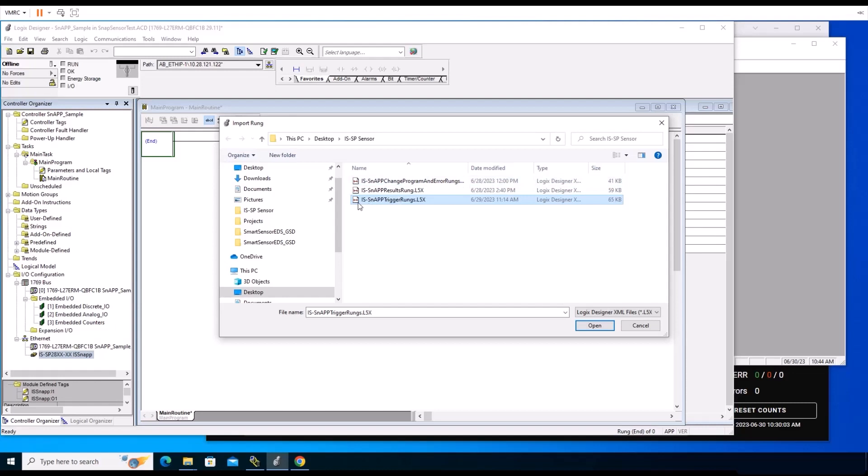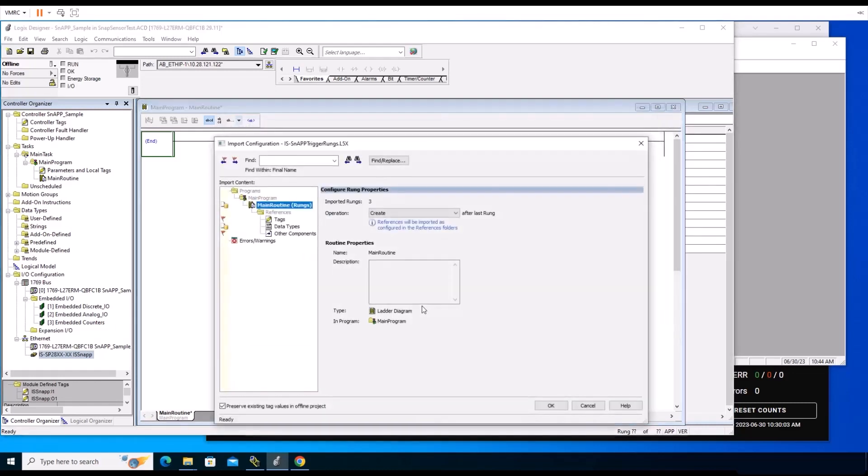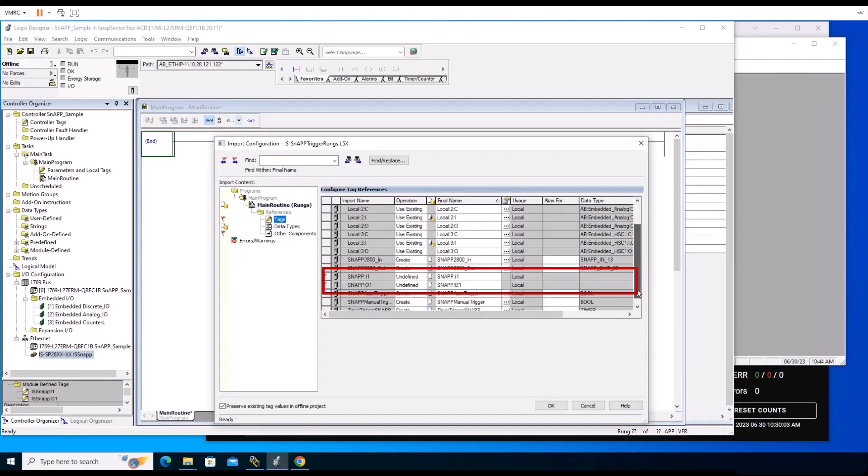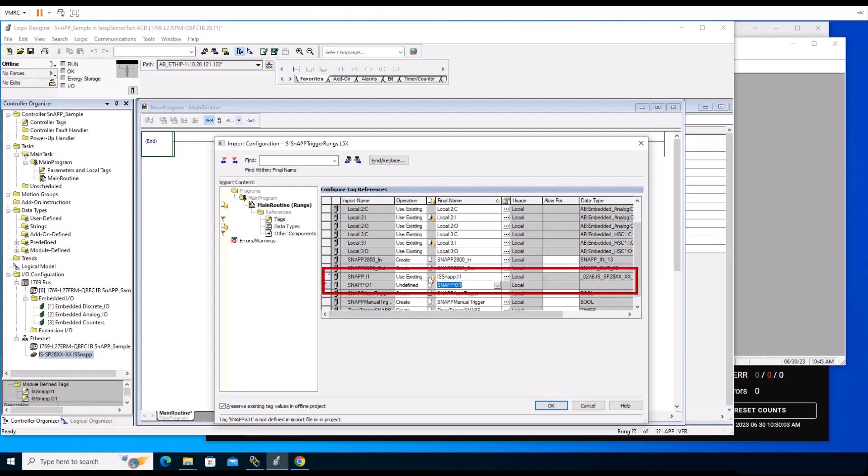You will see a list of imported names within the Configure Tag Reference panel. Identify which import names are labeled as undefined. You'll need to change these to the operation use existing by renaming the default InSight SnAPP name to the name you chose previously. There are three imported sets of rungs provided by Cognex which are available to use: triggering, read inspection results, and change programs. When the import is complete, these rungs will be visible.